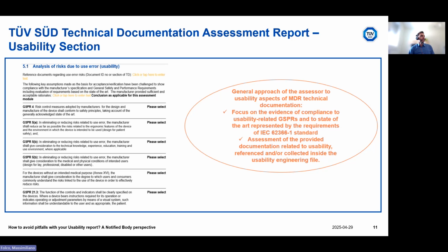The assessment is done mainly taking the usability engineering file from the MDR technical documentation. So the first document that I search in the MDR technical documentation when I start to fill in this section is the usability engineering file that should be provided by the manufacturer as required by the standard 62366.